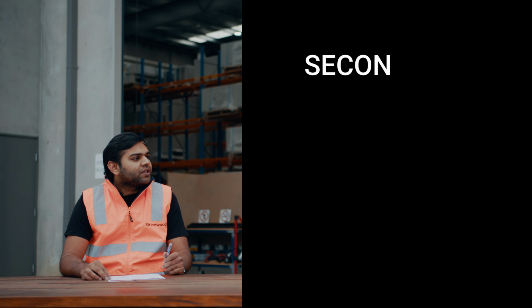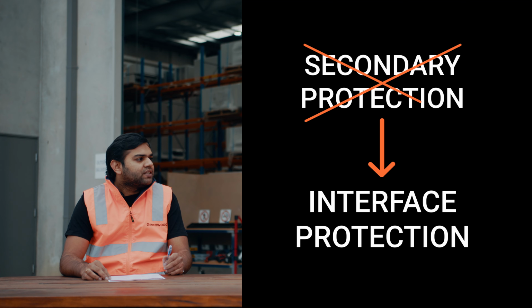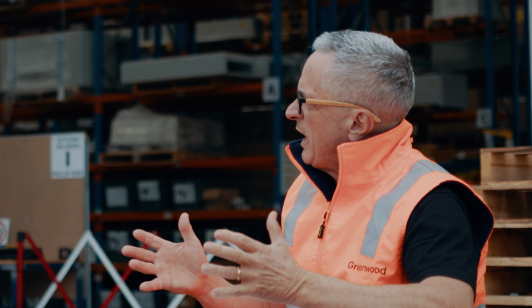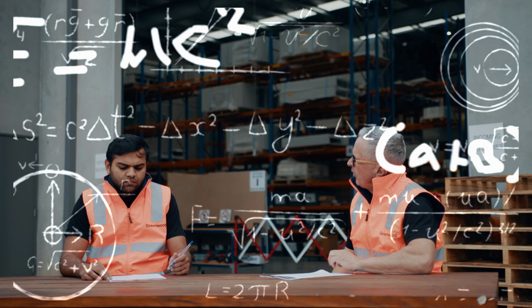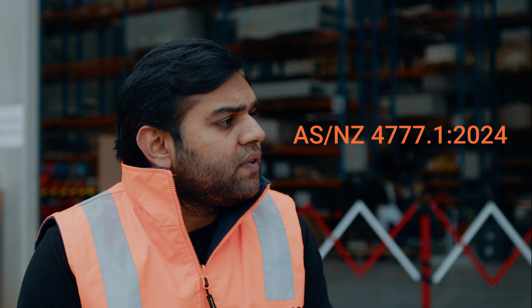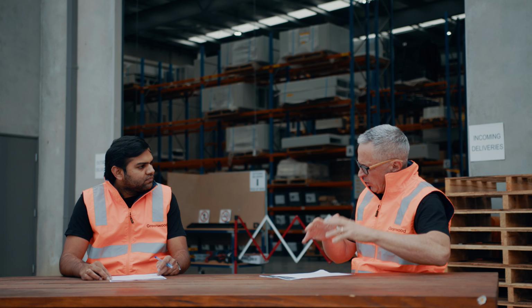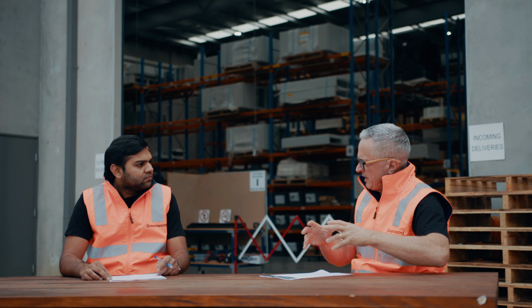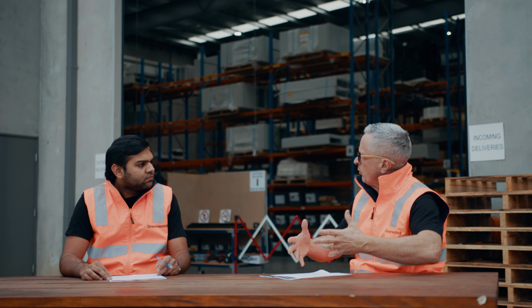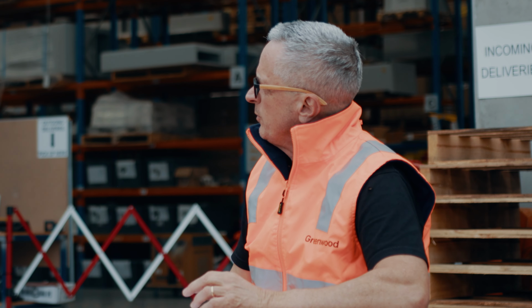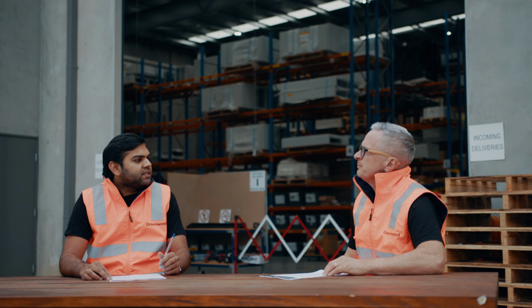Yeah, one of the key changes here really is the requirement for the interface protection, which was previously known as the secondary protection. Could you explain the clause 3.4.5.1 in plain English? It states that the interface protection relay would be required for the system greater than 200 kVA. So that clause is just specifically for the capacity change when it comes to what's required from an interface protection. Yeah, exactly, that's correct.